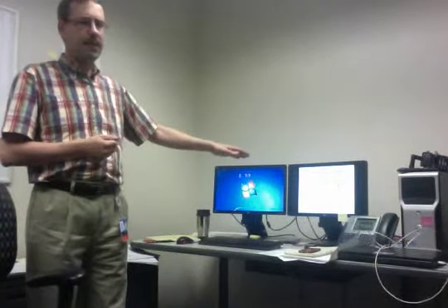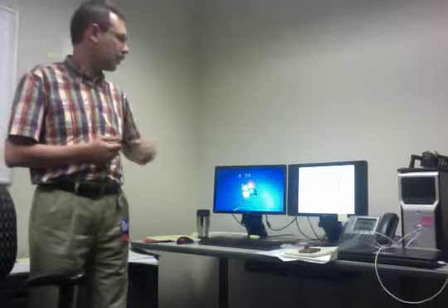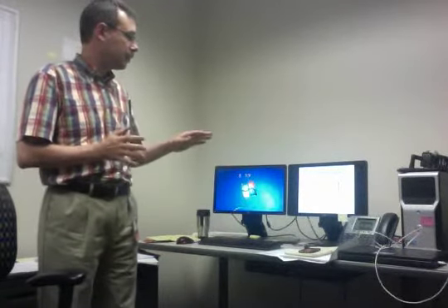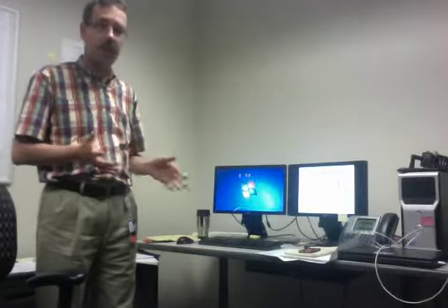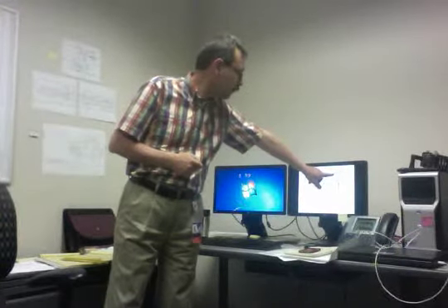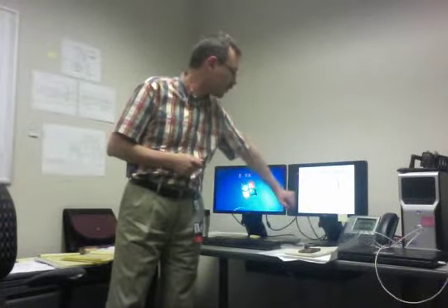I've attached here a roughly drawn distribution substation. Distribution is good to illuminate what's going on because it's a very simple system. It's a one-way system. All the power flows in, as it does here. We've got a 69,000 volt bus with a circuit switcher and a capacitor bank. The red arrow here is the 69K flow of power in.